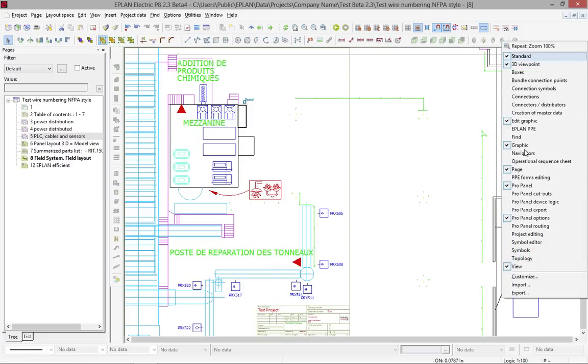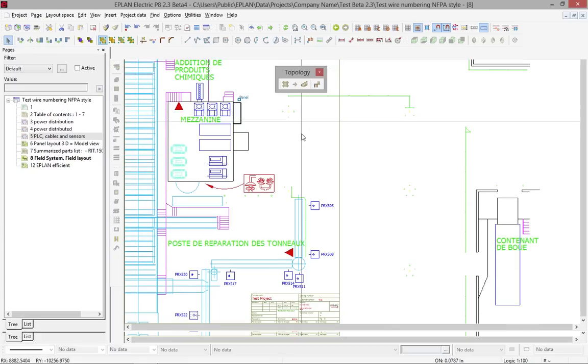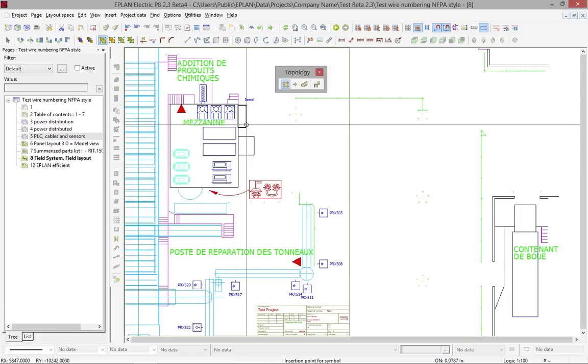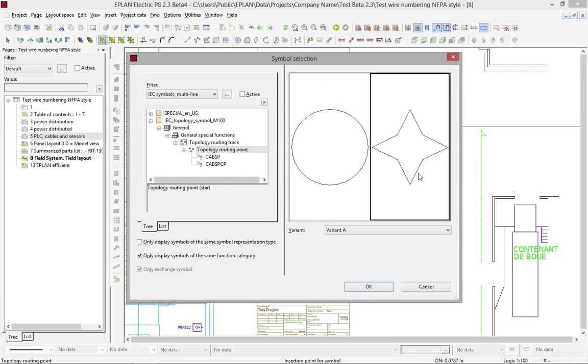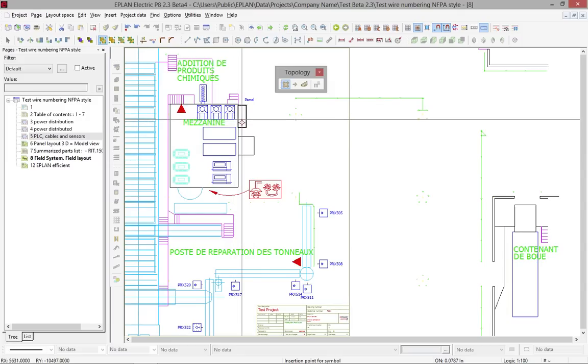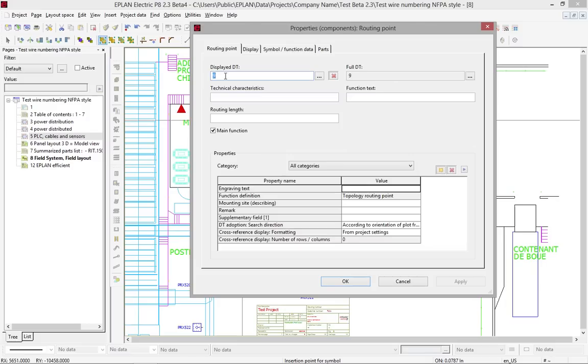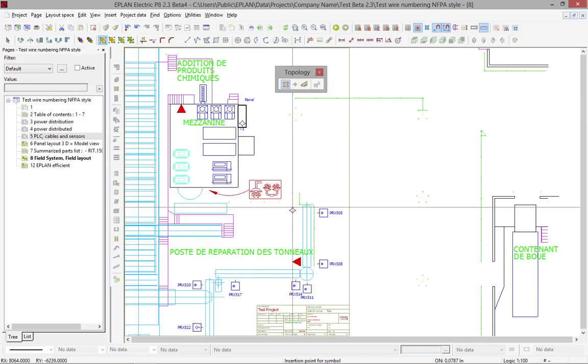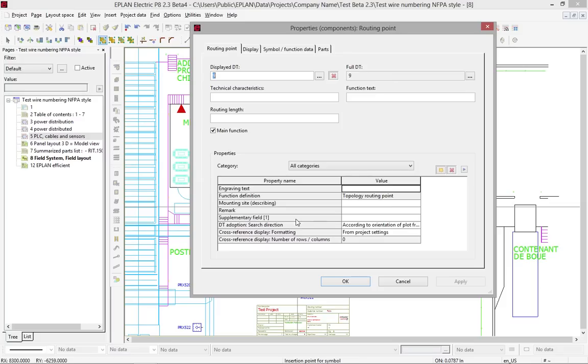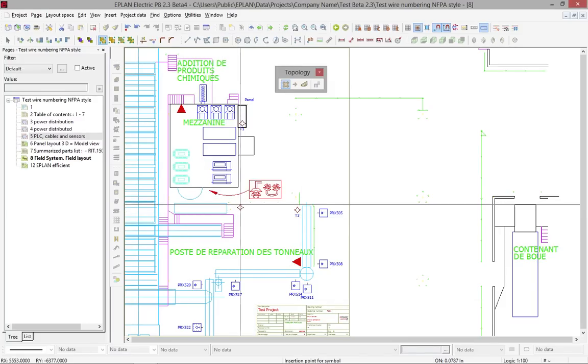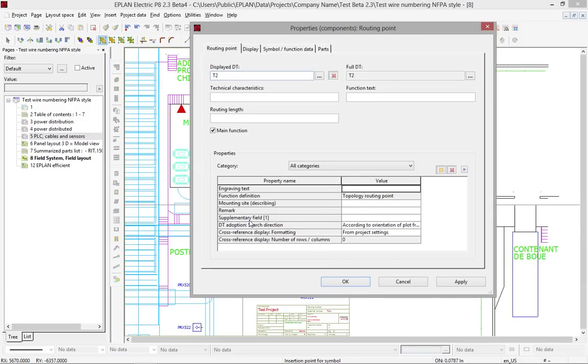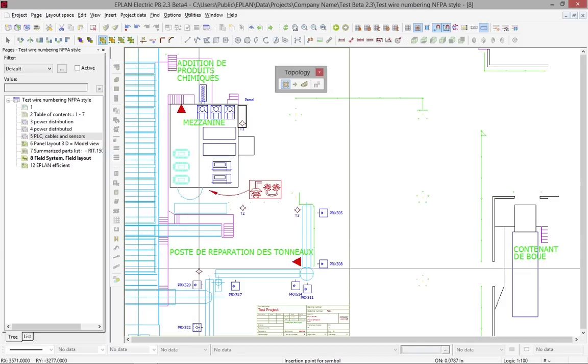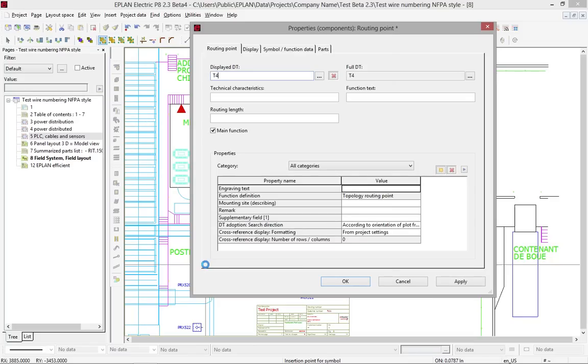Look for the topology toolbar. The topology toolbar has a routing point. Routing points are actually entry points and outgoing points. You can select which symbol you want - you have the choice between a routing point or just a star like this. It's basically an entry point to your cable trace. I'll call it entry point 1 in the panel, and because it's topology, I'll call it T1. Then there's another point here that comes very close to the first conveyor, this is maybe T3. Because I want a junction box right in this area here, roughly, to actually like a splitter - that's going to be my T2. And I want a splitter that actually splits out to a different area, which will be my T4.